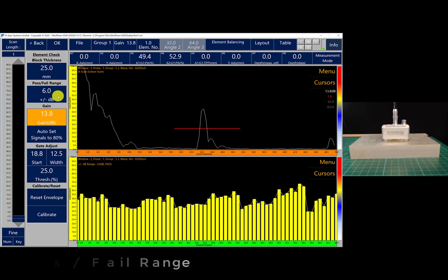Step two would be to set the pass-fail range. The pass-fail range is the maximum signal variation allowed from each element. For the calibration to pass the element check, each element must be within the pass-fail range. You are able to adjust the range accordingly to your standards. We have set the range to be plus or minus 6 dB.